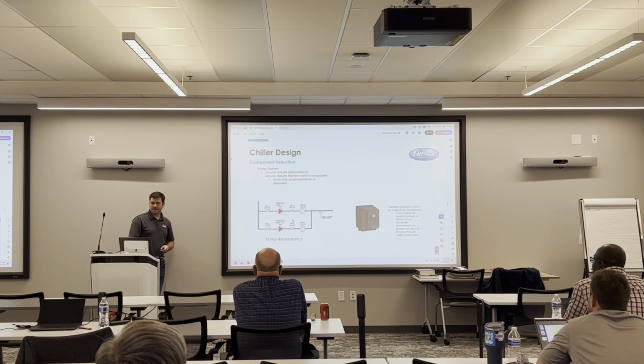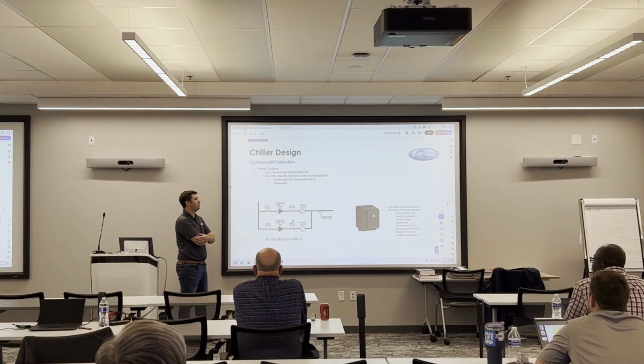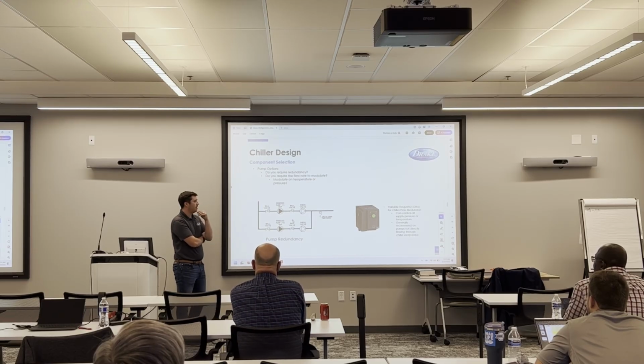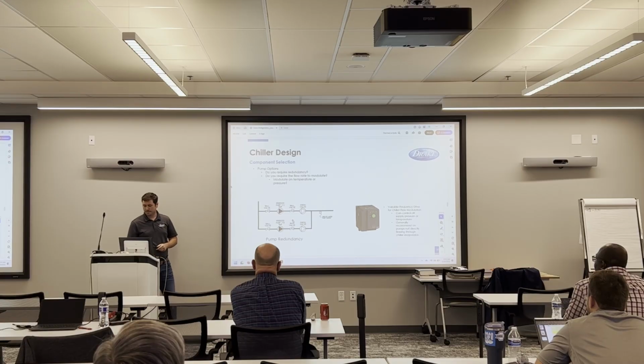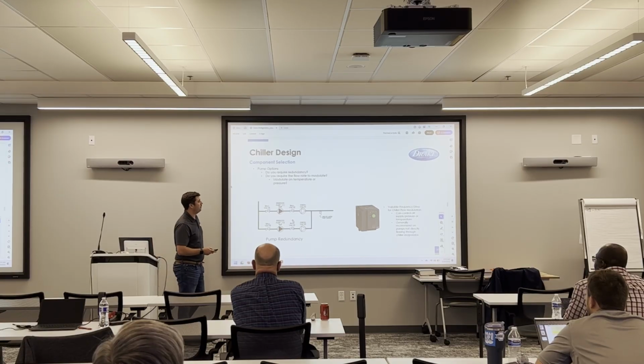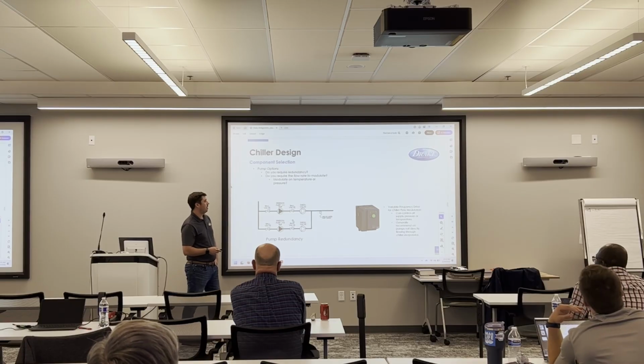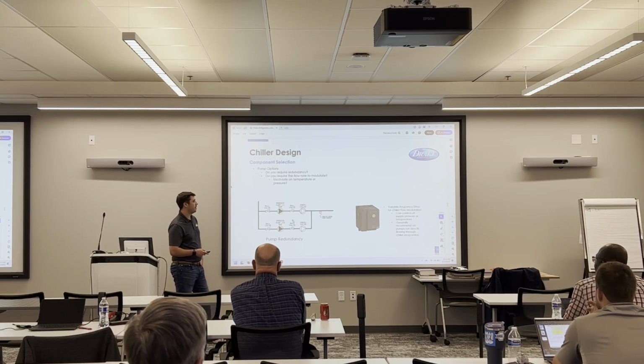We also ask questions like, do you want your flow rate to modulate? There's certain processes out there where they don't always want 50 GPM or 100 GPM. Sometimes the flow has to modulate to work with their process a little better, specifically in breweries. And we'll get into that when we start talking about some different types of industries here. But if they want to modulate the flow, we'll install a variable frequency drive for the pump motor. It can control supply pressure, supply temperature.